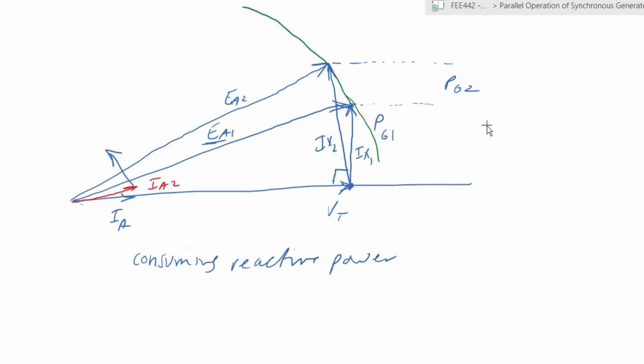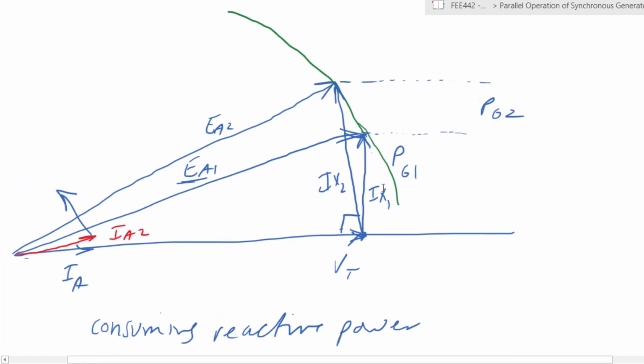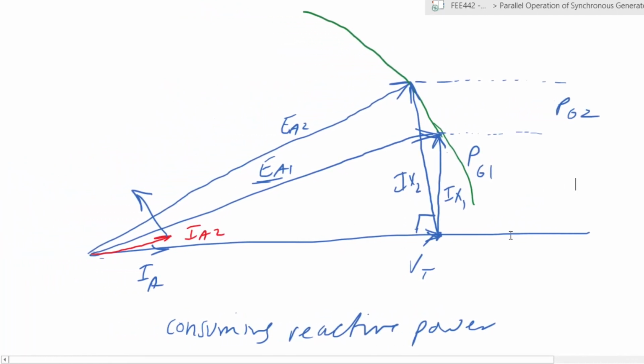If we have your system looking like that, we have increased our power from the initial point, which is PG, to PG2, but we realize that we are now consuming reactive power. Our power factor has gone off. So we want to return it back to this point, which will enable us to have the PG2 that we want, but at the same time a good power factor. So that would then mean you have your EA3 now moving across to PG2. How do you achieve that? You notice that this EA3, the magnitude has now increased.